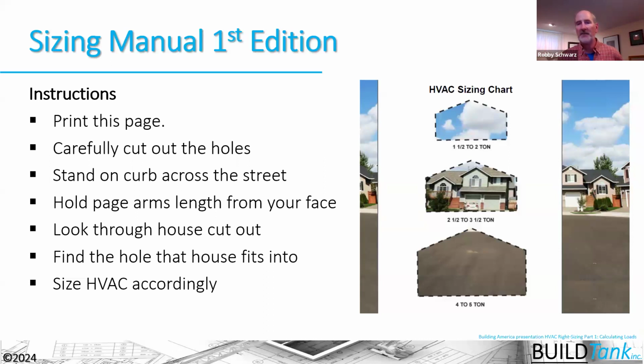Not very scientific, but the reality is that people would do that in a variety of different ways, these guesstimates, to be able to size the systems in our houses. And what we've learned over time is that oversized systems don't perform efficiently. They don't work. Their coils freeze up. Their airflow is off. All these things. So as we're gaining that control and predictability, we also want to gain control and predictability of the HVAC design, meaning that we want to right size the equipment that we're putting in that house.